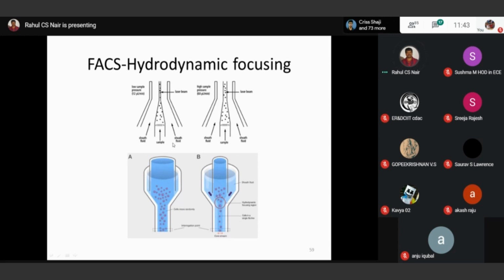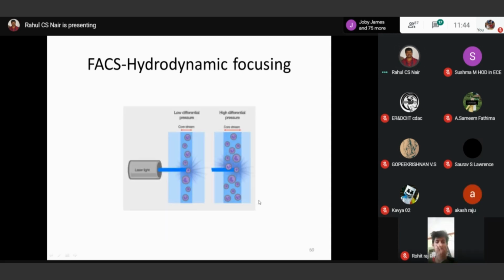While discussing this, one thing worth mentioning is hydrodynamic focusing. Hydrodynamic focusing means that you can focus the solution containing the cells to be analyzed by means of a special fluid called a sheath fluid. The sample jet is introduced through the middle of the sheath fluid so that the sample stream remains intact and can be analyzed. Each cell can be analyzed individually. I can show you the details of it.